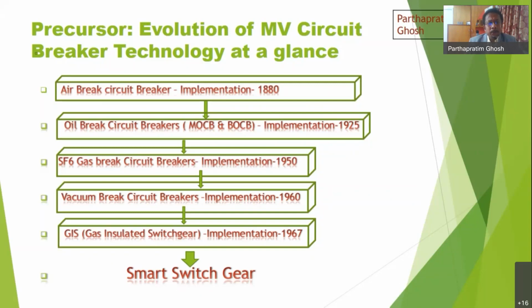And the next technology was the vacuum circuit breaker, which is still evolving. It is very predominantly used in the medium voltage segment up to 33 kV. Now R&D action is still going on to implement it at the EHV segment also, that is 66 kV and above. Some implementation is there for 66 kV, but beyond that it is still under development and commercially not viable.